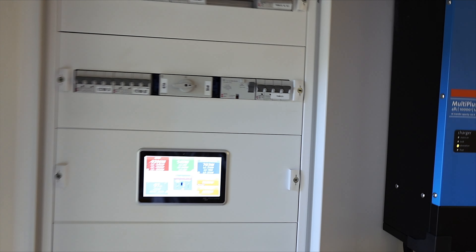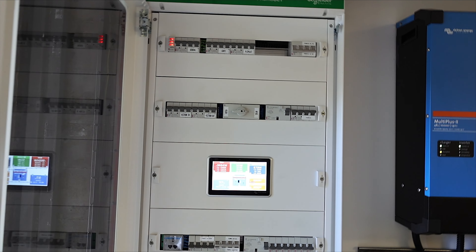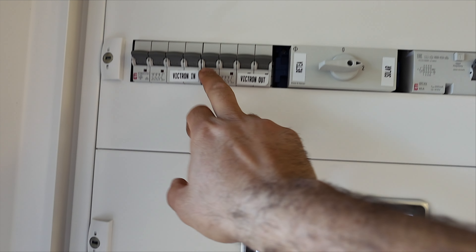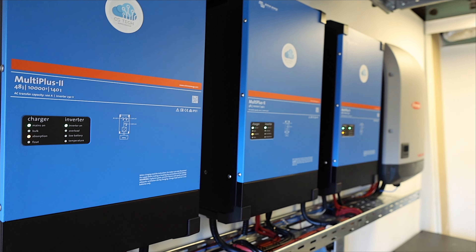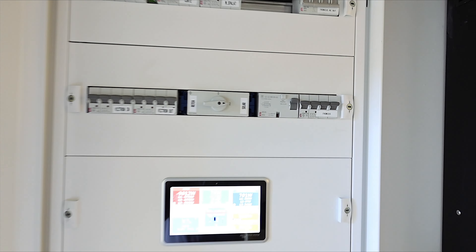Now let's talk about protection. As you can see, I have the cabinet from Schneider. I decided to install all the protection from ETI — a company we've been working with since 2006 or 2007. They are very efficient, so I also installed their products in my home. For example, I have a switch here with three positions: Victron in, Victron out, solar, and grid. The reason I installed this switch is so that when it's connected to solar, the entire house consumption goes through Victron. For different reasons — such as a Victron update, upgrade, or fault — I simply move the switch to grid, and the entire system bypasses Victron so my home is connected directly to the grid.